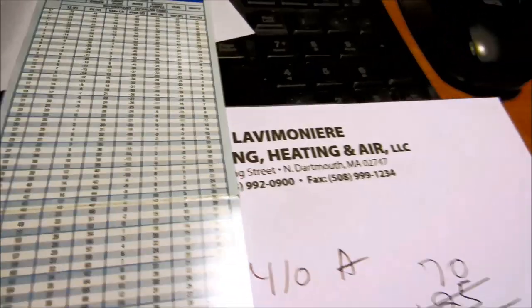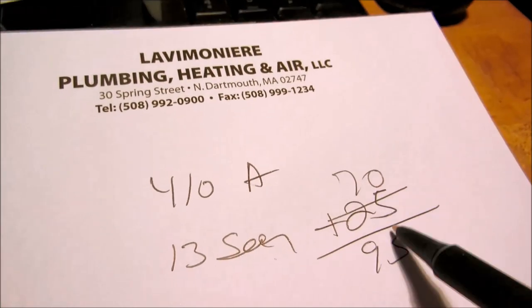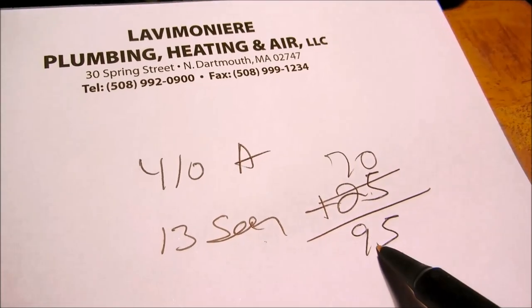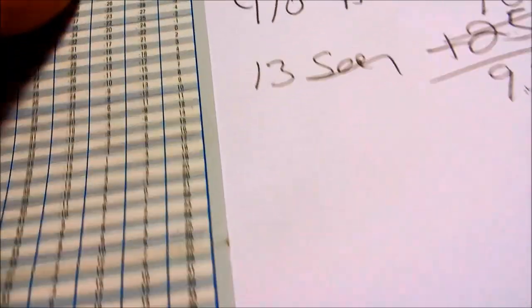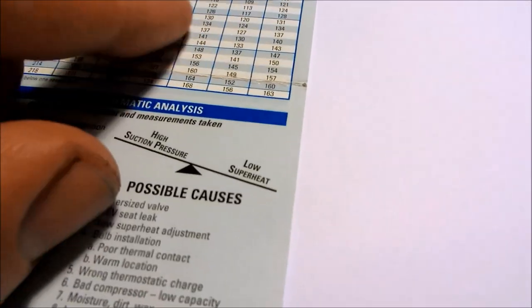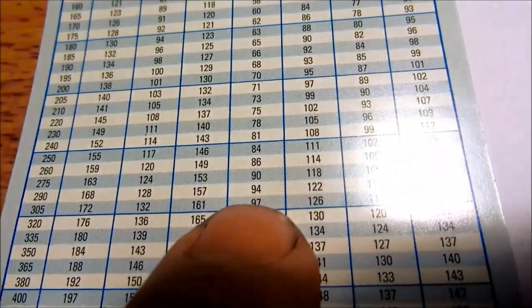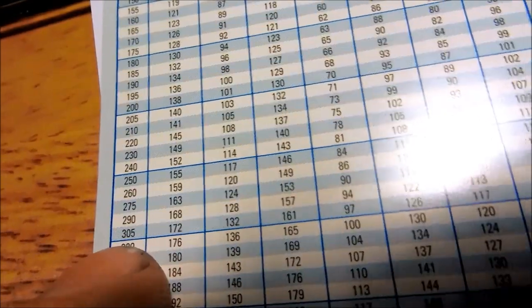Let's do the 410a. Say 410a 13 SEER, 70 degrees outside plus 25 would be 95. What should the head pressure be on a 410a system at 70 degrees ambient temperature? We're going to go down to 95 on 410a.